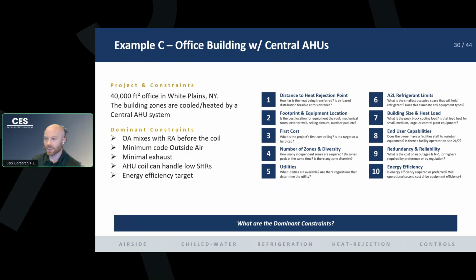Our air handler is going to be located in a mechanical room, and you just dump your outside air into the room or into the mixing box of your air handler, and that outside air is going to mix with the return air before it reaches the coil. In an office building, there's going to be minimal outside air. It's just your people and your square footage load per code. There's not a significant exhaust here.